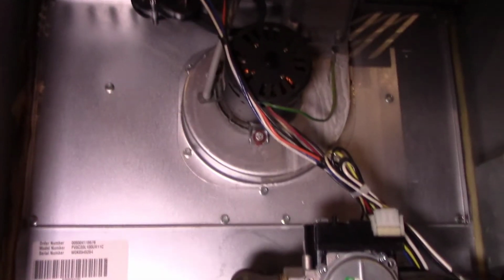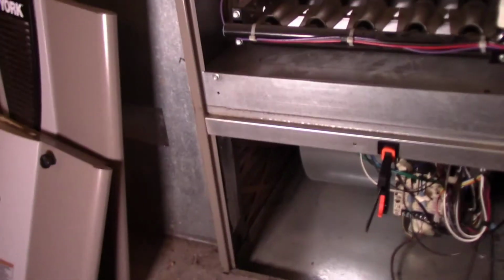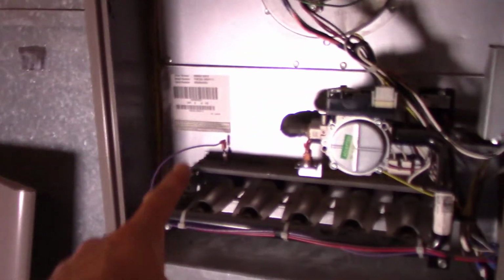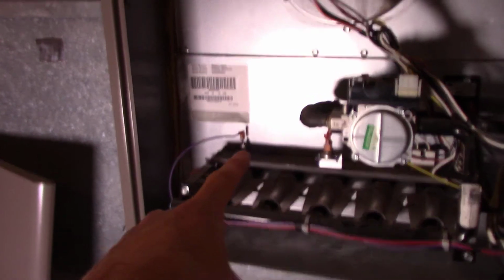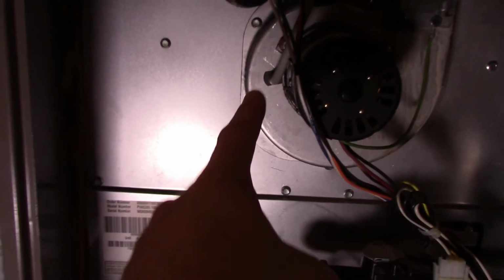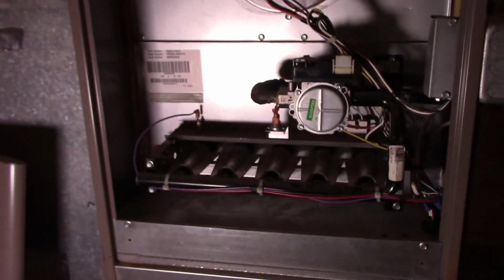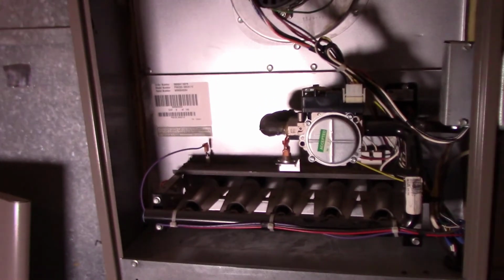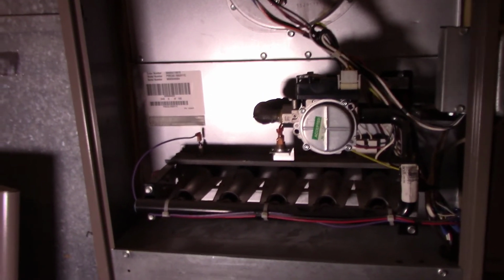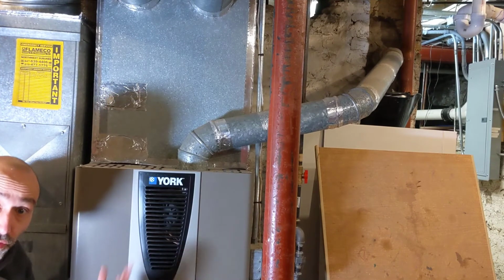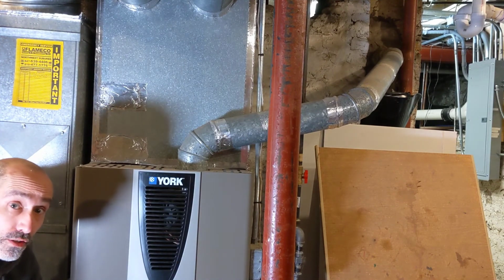Because it's pulling the air from your fresh air intake into the blower motor and then up and out your duct. Those are the three things: the furnace filter, the flame sensor, which I just showed you how to clean, and the inducer port. If you keep those things clean every year, you will likely have no problems with your furnace for a while.